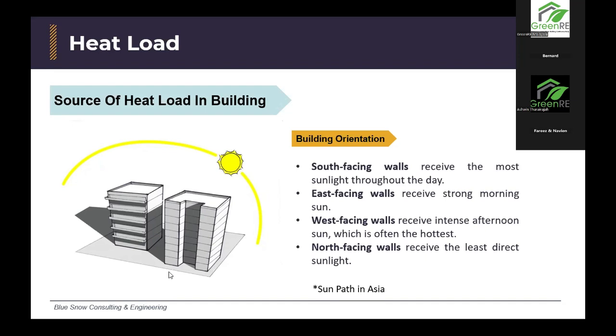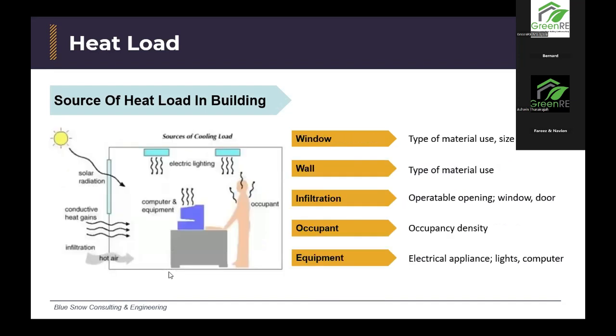this orientation should be considered as well. The next one is the heat from inside the building itself, not the exterior parts like the sun. The first two are the window and wall. The window depends on the type of material used, and also the size, depending on the U value of the material used. So window and wall can be considered as the same category. The next one is infiltration, which is caused by operable openings like operable windows and doors. The next one is occupants. This is determined by the building occupancy, and it will affect the latent and sensible heat in the building.